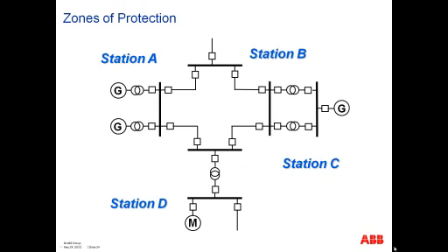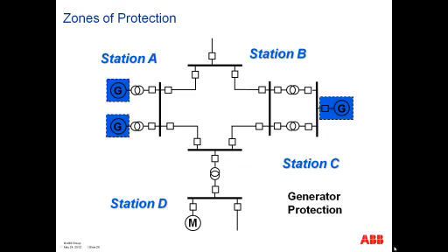There you go. We'll start off with a simple power system here, where we have station A, B, C, and D, and we will first show our zones of protection for the generators. And in both cases, the generator would operate the breaker if it's a breaker tied directly to the generator. It would of course trip that.